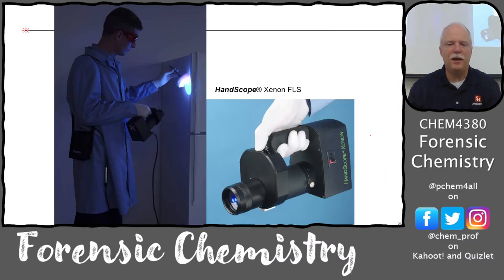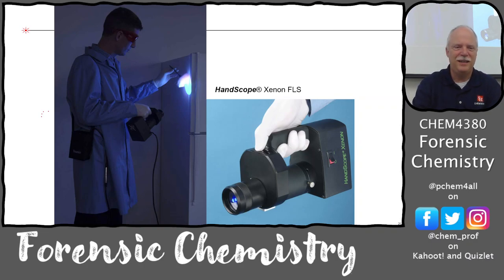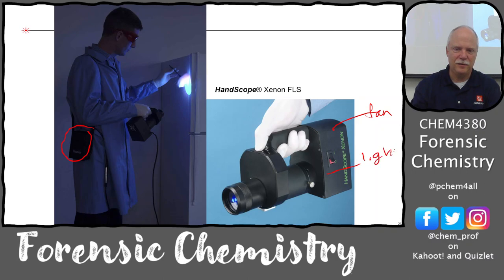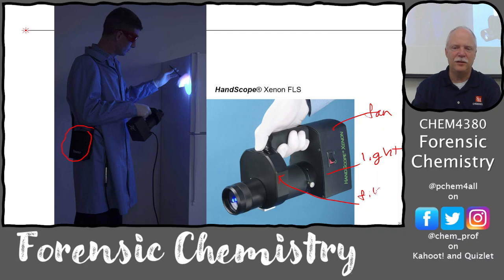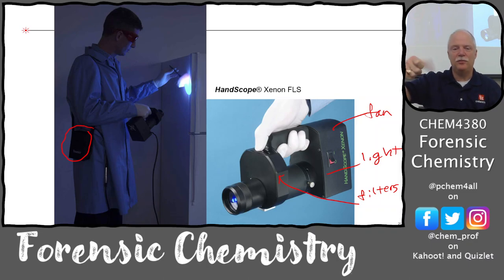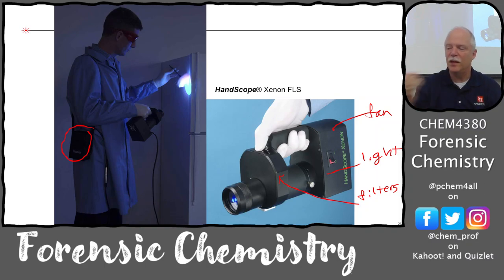Here's the handheld xenon scope — kind of big and bulky. Some have a battery pack on the hip with a cable. In the back is the fan and the light source. In the little housing with a thumb wheel are the filters — seven filter wheel positions. Very handy: you can switch to UV, blue, orange, yellow, all different source filters. It comes with different goggles — clear ones are important because UV light with long exposure can cause cataracts, and that's why you should wear sunglasses at the beach.